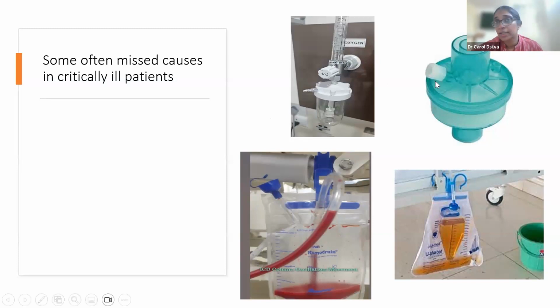HME filters often get clogged and blocked. Also, if one of the caps is loose, that can also give rise to leaks, something that's very difficult to pick up until you have an eye for it.